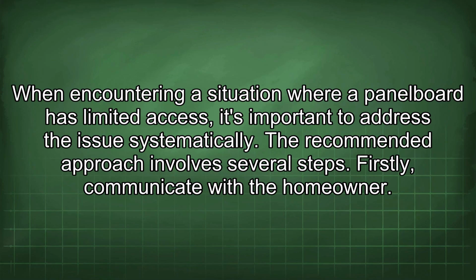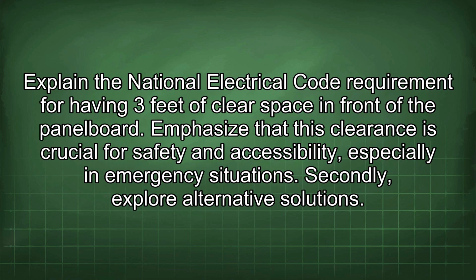When encountering a situation where a panel board has limited access, it's important to address the issue systematically. The recommended approach involves several steps. Firstly, communicate with the homeowner. Explain the National Electrical Code requirement for having 3 feet of clear space in front of the panel board. Emphasize that this clearance is crucial for safety and accessibility, especially in emergency situations.